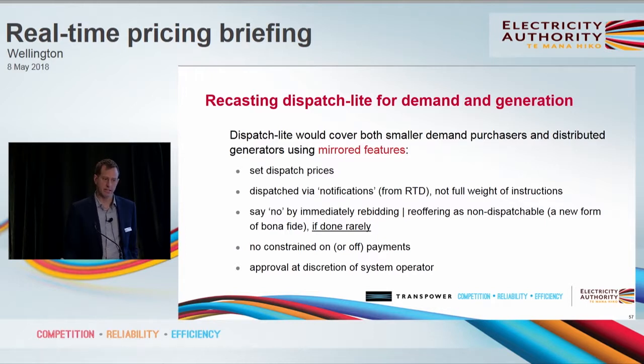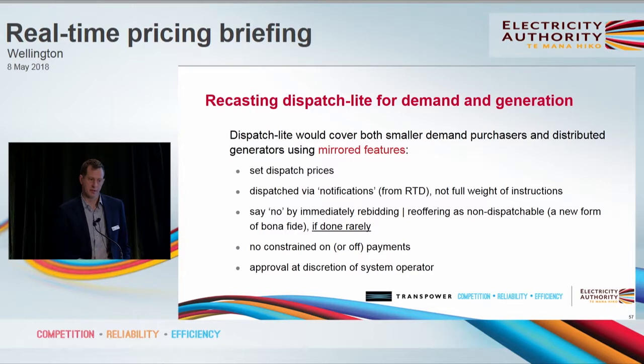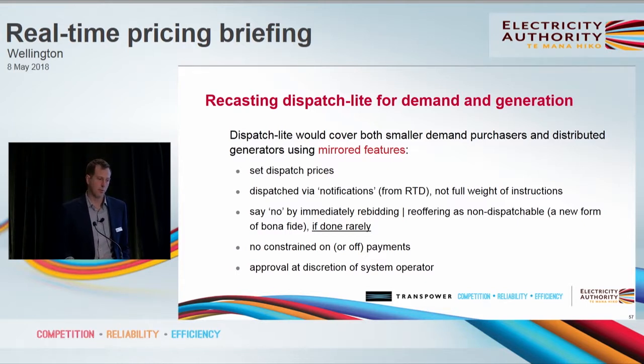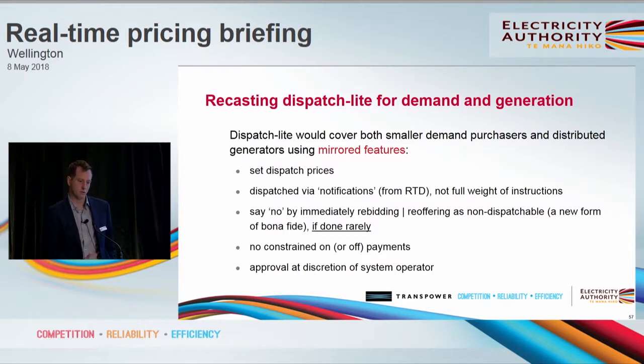What we're thinking now is it's just a pair of products using essentially mirrored features. Both would be able to set dispatch prices, both would be dispatched using notifications from the real-time dispatch schedule, and those notifications don't have the full compliance weight of dispatch instructions. That means you can say no if you do it rarely, and you would say no by rebidding or re-offering immediately. You would become non-dispatchable at least until the end of the trading period, and that's another aspect we'd want to consult on — how long should you be out when you say no.